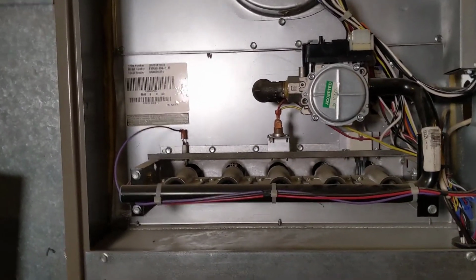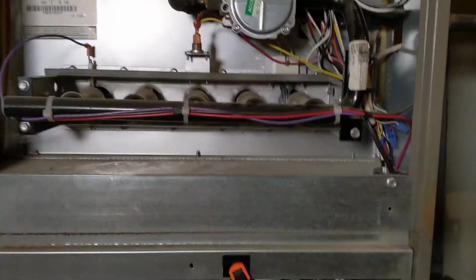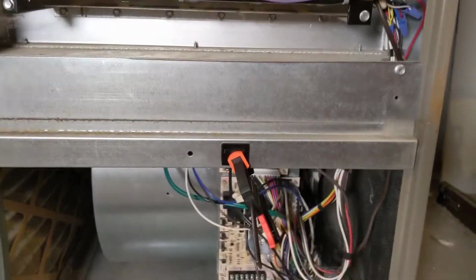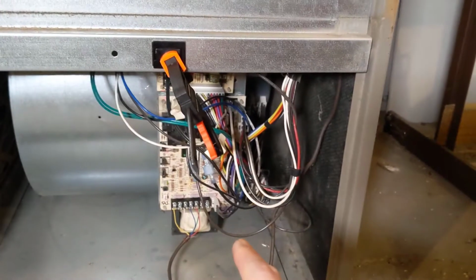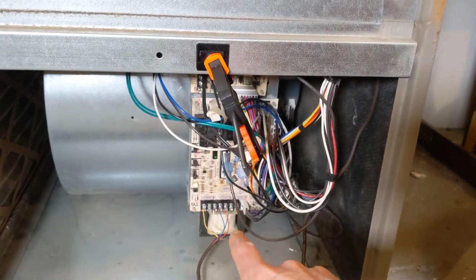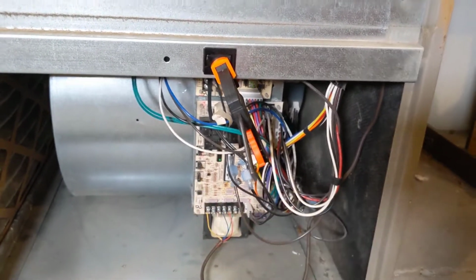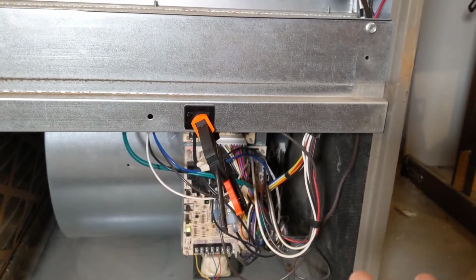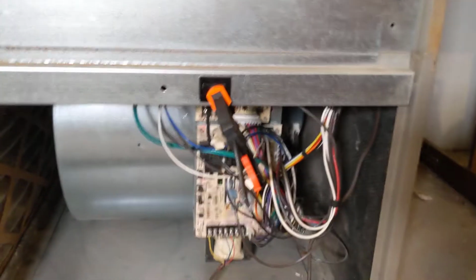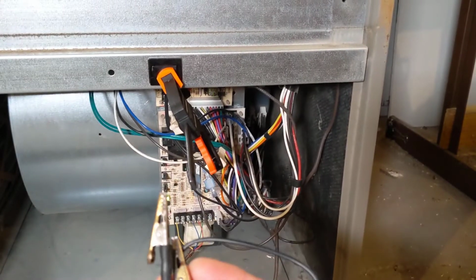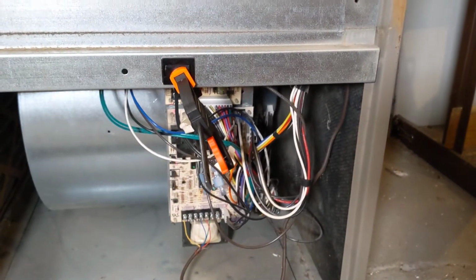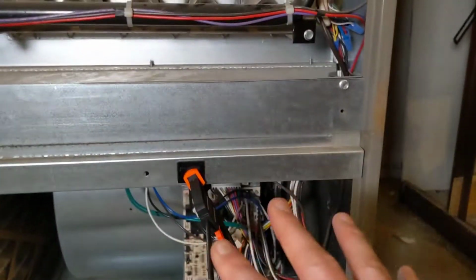Okay, so at this point we know we have power coming in. We know we have gas and everything like that. So let's go back to troubleshooting here. We've got power, we've checked our fuse, we have the light on our board. We've got our indicator light. So everything looks good, and we know we've jumped out. Let's say we've either jumped out our thermostat or we just know our thermostat's calling for heat, but nothing happens.